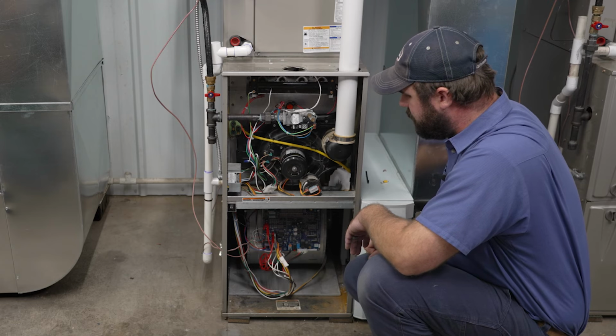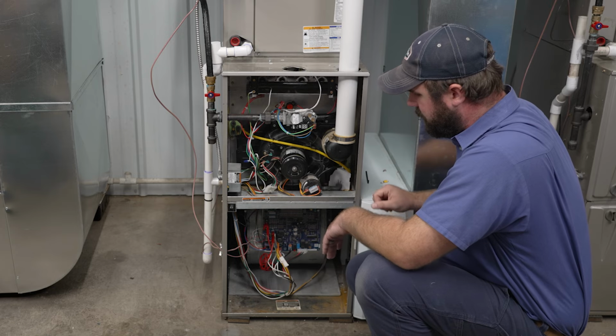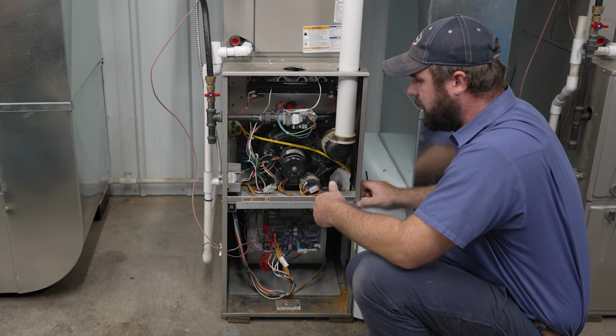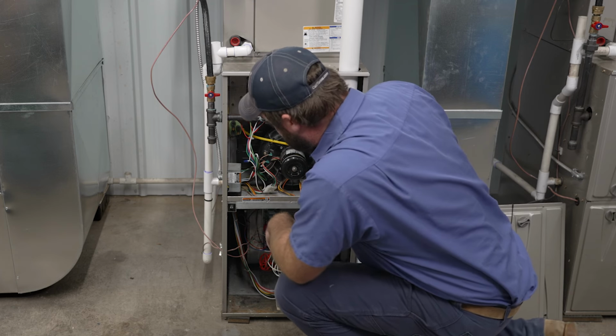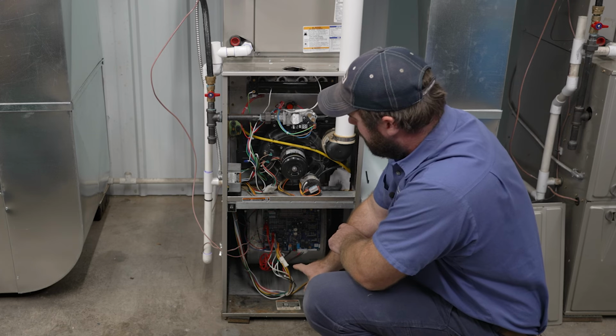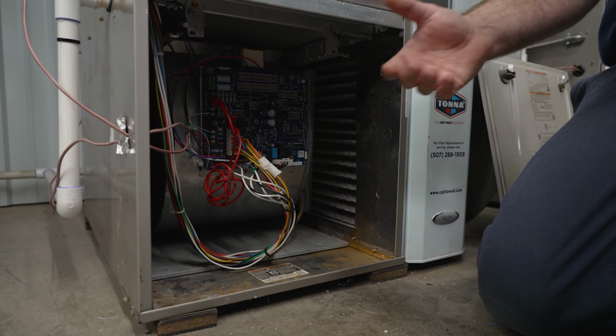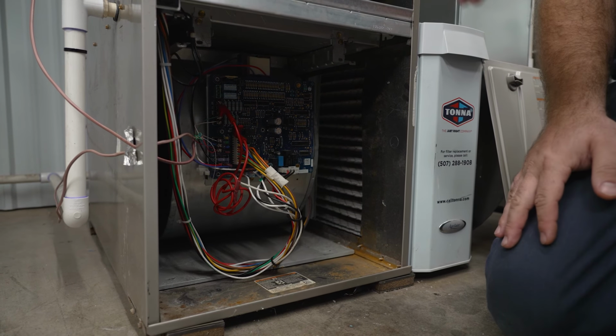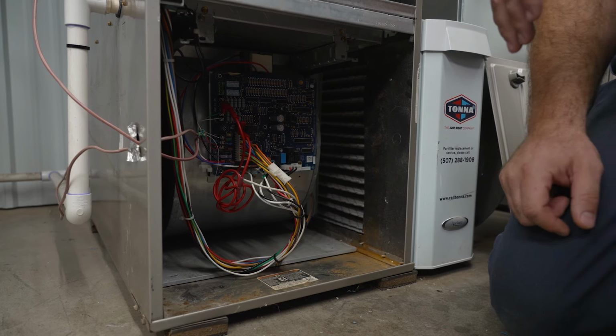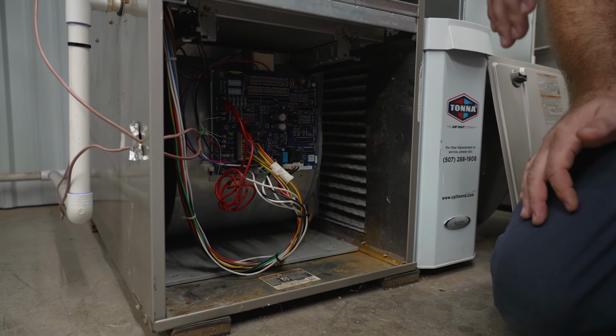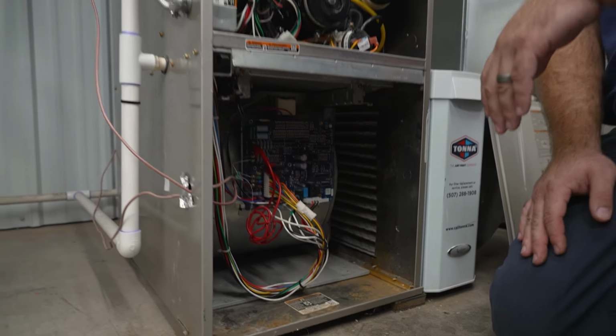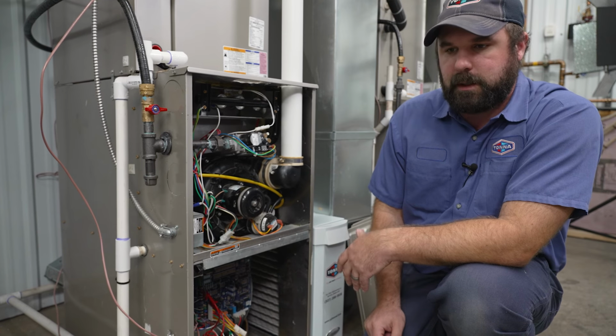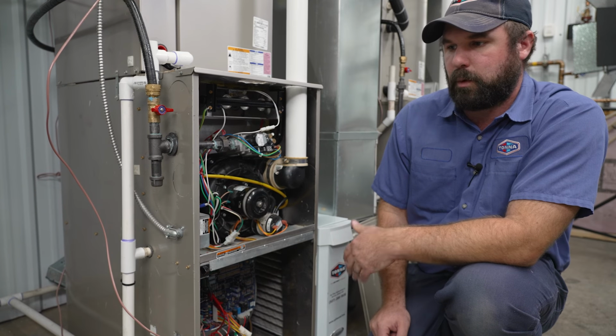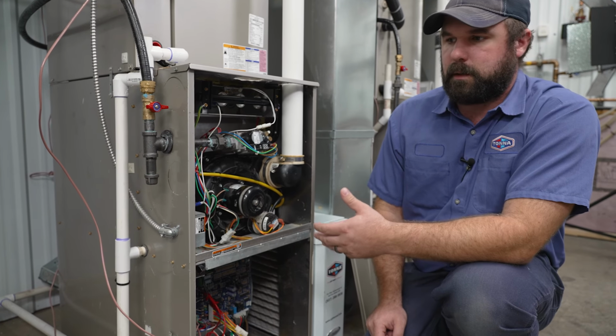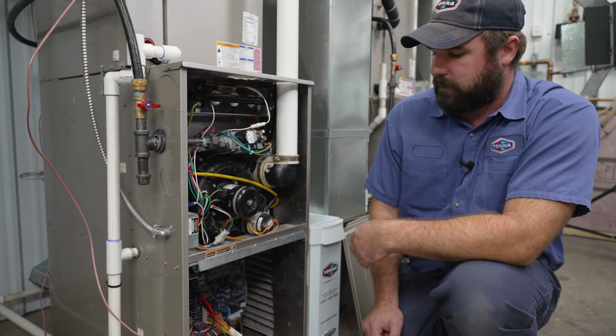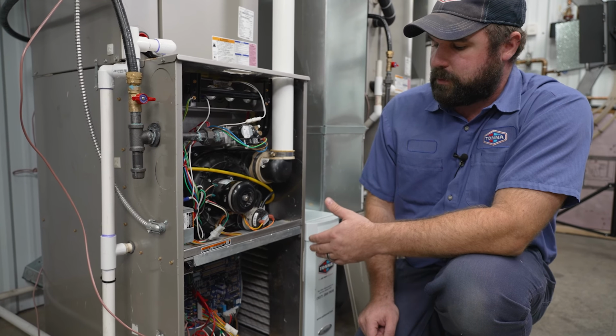Now, one other thing we do check, and you won't be able to see it, so most of us will take a picture of this so you can get a visual look at what kind of condition it's in inside here, is your blower wheel. That's what moves the air through the system, through your ductwork, pulls it back through your returns and then out your supplies. We want to make sure that's clean and free of debris. If it's dirty, then we will have some efficiency issues, and your system will be more likely to break down. Keeping that clean ties back into your filtration. Having a good filter in place ensures that it stays clean.